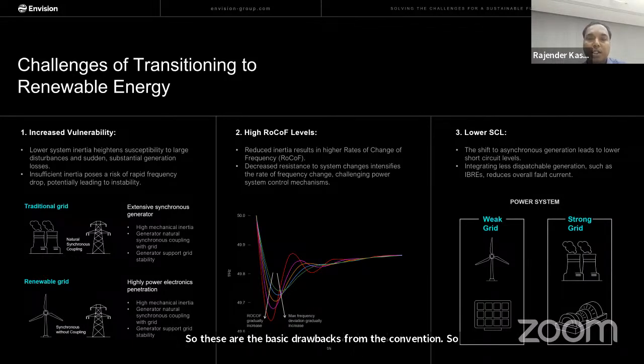During any fault condition, the suppressed voltage magnitude and potentially distorted waveform may lead to the converter falling out of step and having difficulty catching up. This can also lead to hunting behavior, where the solar inverter produces an active or reactive power oscillation loop. The fault current is also the third point.